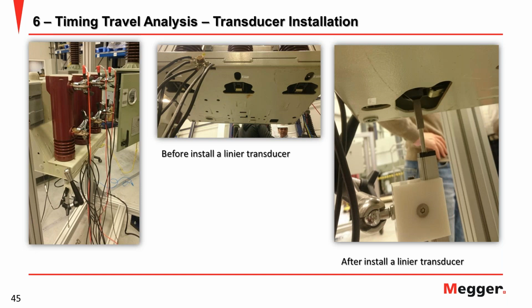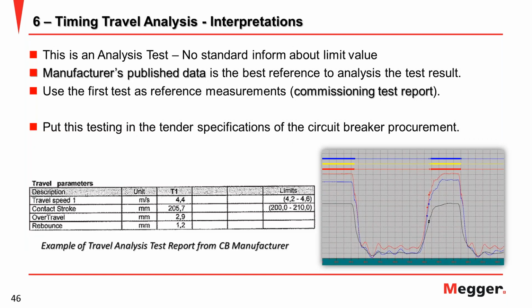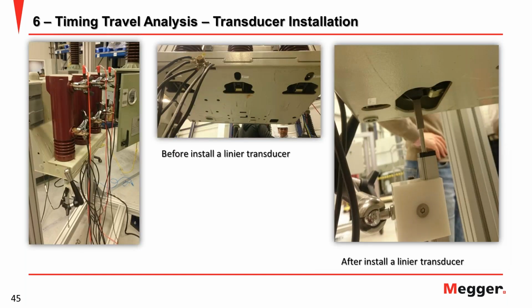But I know in the real condition it's not possible like this. Mostly on the MV breaker, we are only able to connect a rotary transducer. Mostly close to the circuit breaker part, you can see something rotate, and then you can install the rotating transducer, the rotary transducer.